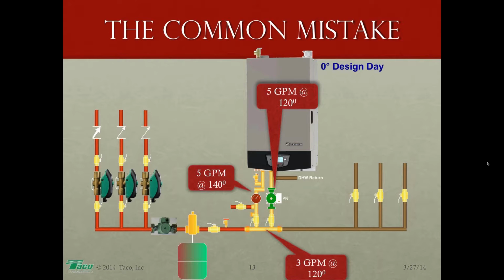And we hear from Anthony Reichow, who is maybe one of the 2 or 3 smartest people I know. You can't be the smartest guy I know, Anthony, because that's Bruce Marshall. You may be number 2. The boiler needs to control the pump speed. So Anthony, a ModCon boiler salesman and a ModCon boiler rep, is very, very adamant about that. System flow always needs to be greater than boiler flow. All right. Very good.